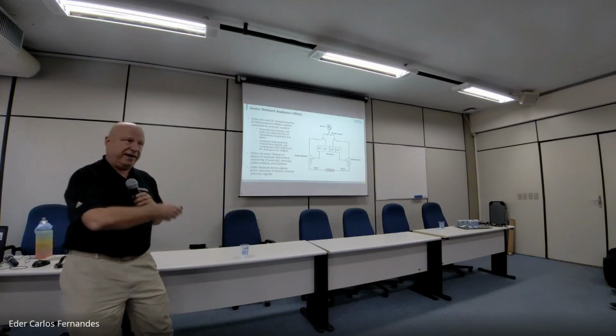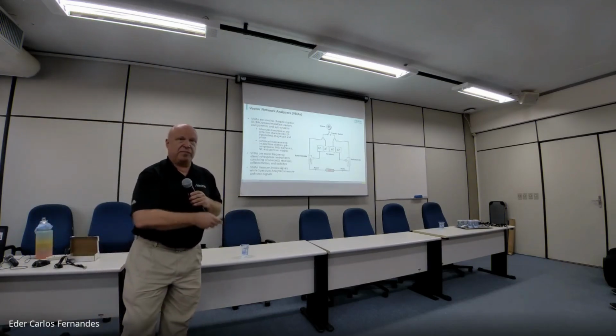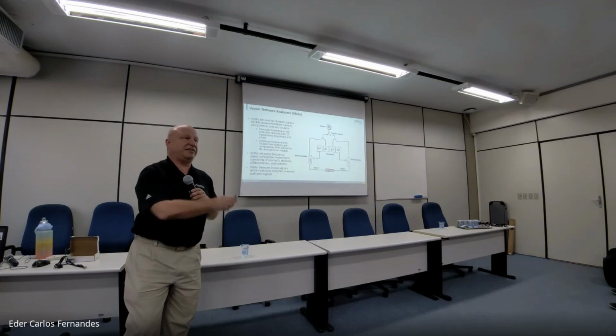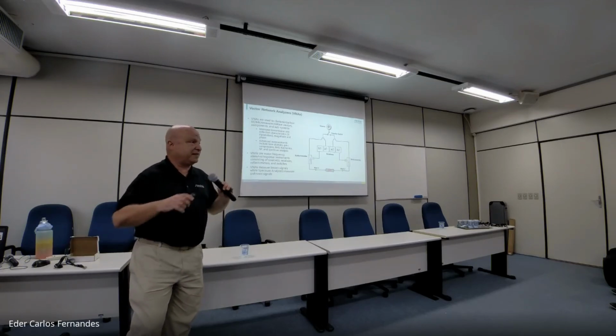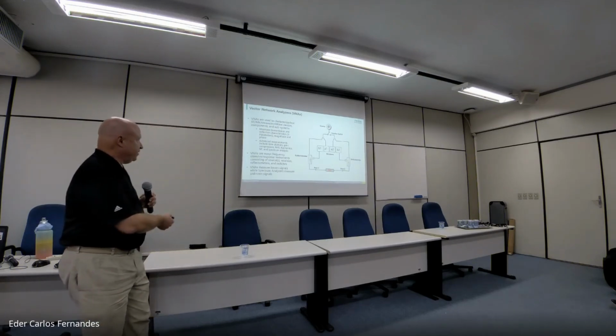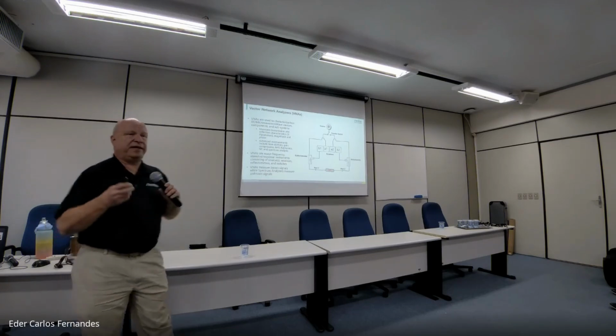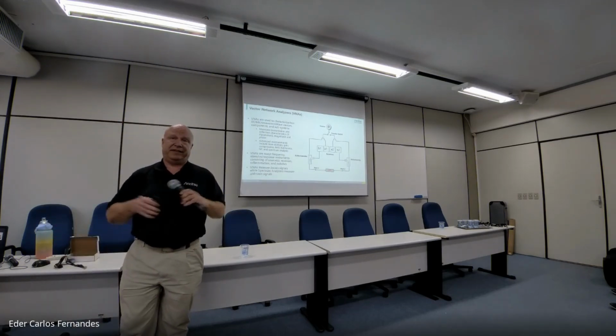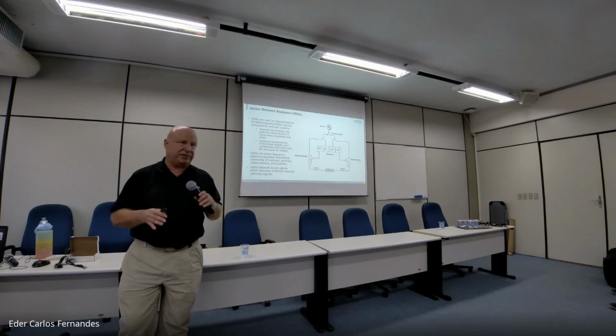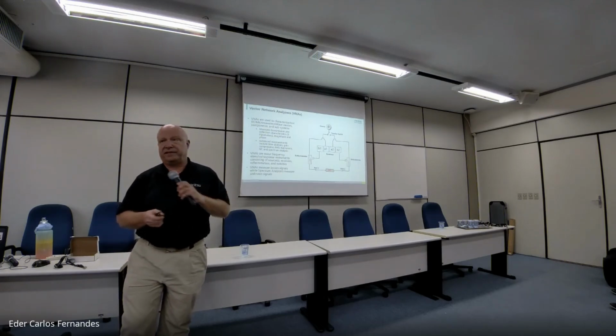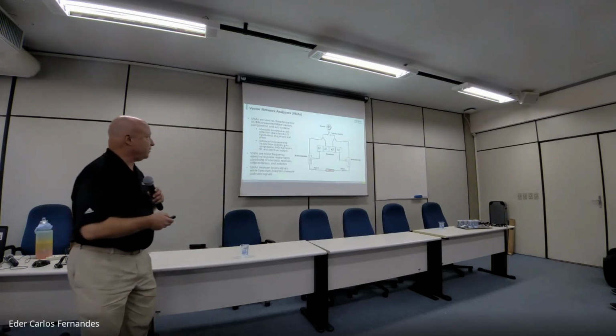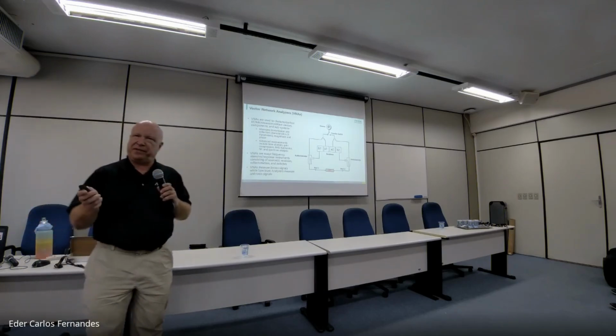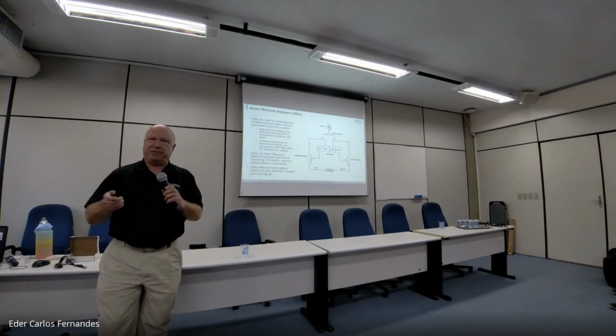A VNA can behave as a spectrum analyzer, but its receiver is never going to be as good as the standalone spectrum analyzer because it doesn't have the same capabilities. It's not designed for that initially. It was designed to do ratioed measurements. This is being used here when you're using it as a spectrum analyzer to make absolute measurements. So again, the receiver detection is different between the two kinds of instruments. But I always like to point that out because most people are very familiar with the absolute measurements that you make in dBm, power.